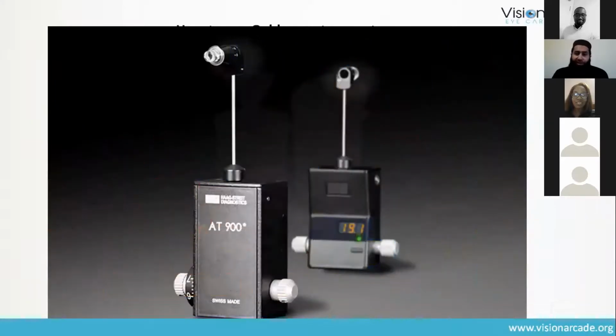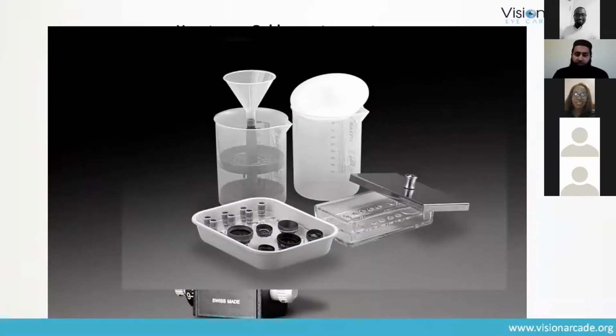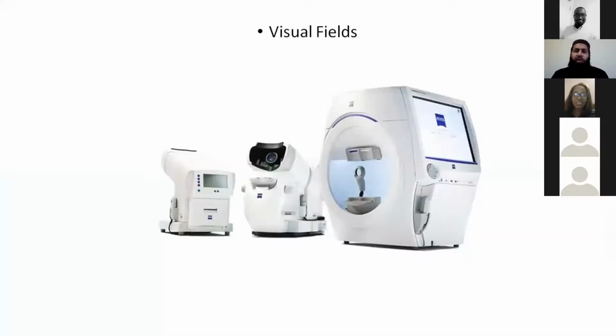And then you need to clean the prisms, and Milton is something that we used to use here. However, nowadays, just to save the risk of cross-contamination and the hassle of cleaning, tonometer-safe is quite a good thing. These are just plastic tips that you can put on top of the prism and take your measurements. The quality of view is not as good as the prism that comes with the Goldmann. However, it's quite handy and quite convenient. You just throw them away after one use.